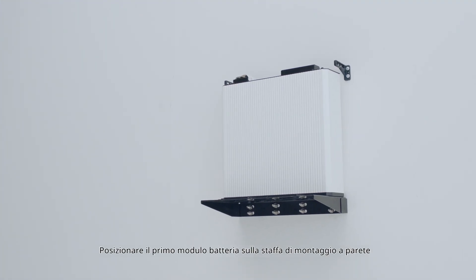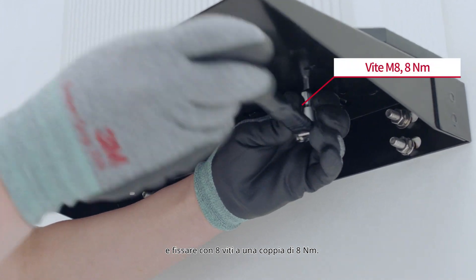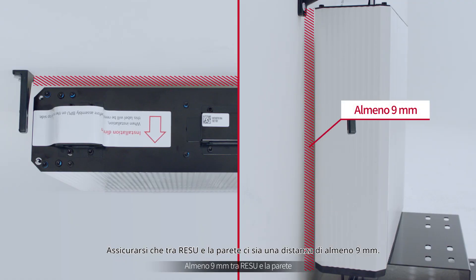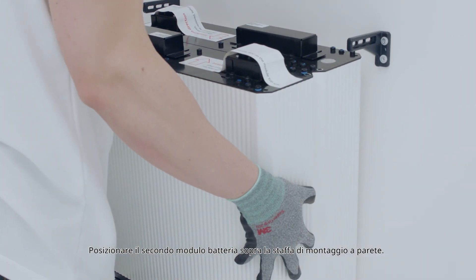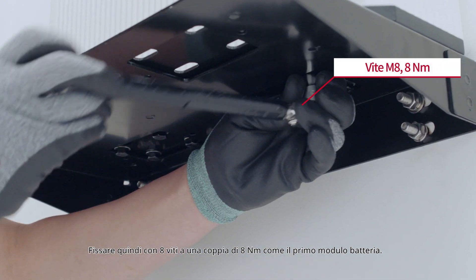Fix the provided mounting brackets to the wall with the M6 screw anchors with a torque of 5 Nm. Place the first battery module on the wall mounting bracket and fasten with 8 screws with a torque of 8 Nm. Check to be sure that there is at least 9 mm between the RESU and the wall. Place the second battery module on top of the wall mounting bracket, then fasten with 8 screws with a torque of 8 Nm, just like the first battery module.